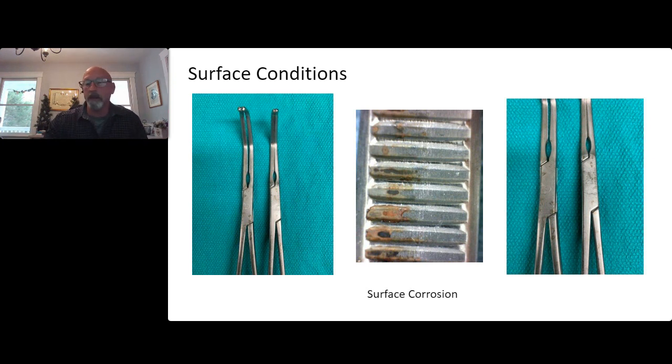If your white tray liners are turning brown, you have issues. Taking the white tray liner away does not fix your problem — the problem is still there, you just may not see it as easily. A lot of people send white tray liners out to get tested, and sure enough it's water elements. Understanding the carryover and how it affects instruments is key.